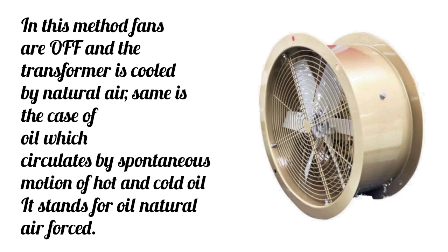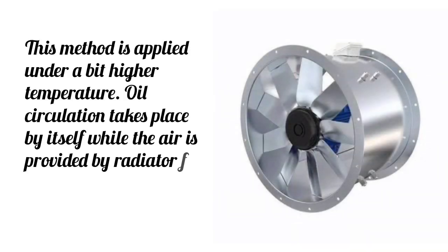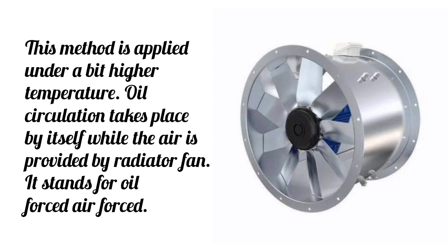ONAF stands for oil natural air forced. This method is applied under a bit higher temperature. Oil circulation takes place by itself while the air is provided by the radiator fan.